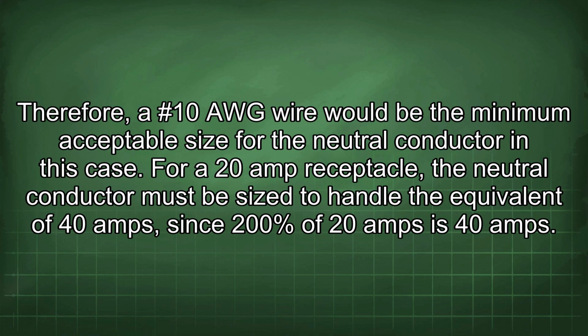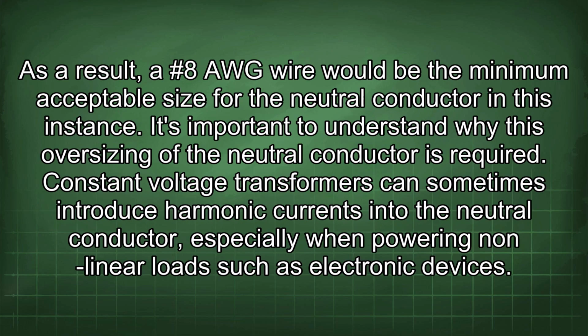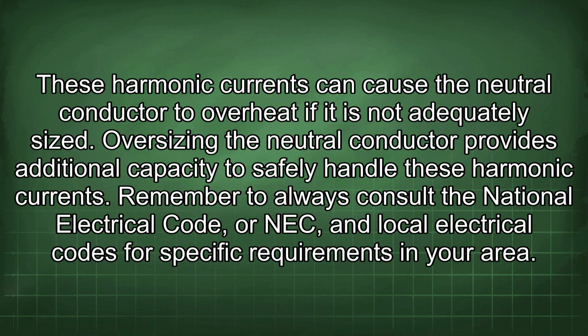For a 20 amp receptacle, the neutral conductor must be sized to handle the equivalent of 40 amps, since 200% of 20 amps is 40 amps. As a result, a #8 AWG wire would be the minimum acceptable size for the neutral conductor in this instance. It's important to understand why this oversizing of the neutral conductor is required. Constant voltage transformers can sometimes introduce harmonic currents into the neutral conductor, especially when powering nonlinear loads such as electronic devices. These harmonic currents can cause the neutral conductor to overheat if it is not adequately sized. Oversizing the neutral conductor provides additional capacity to safely handle these harmonic currents.